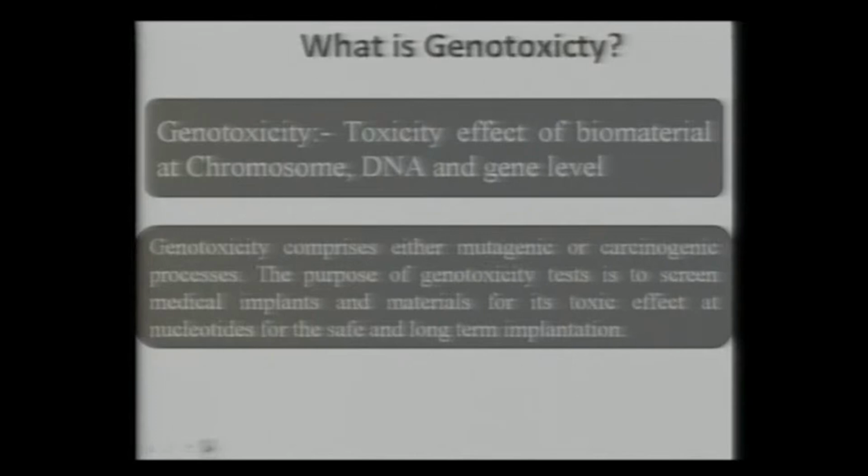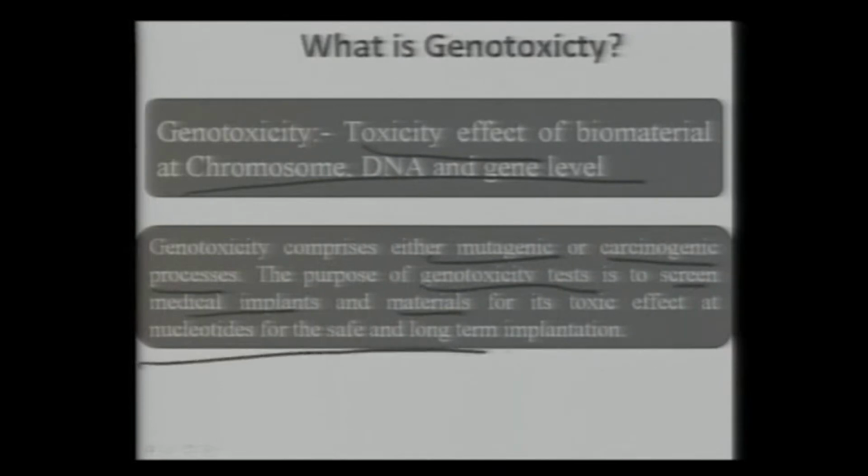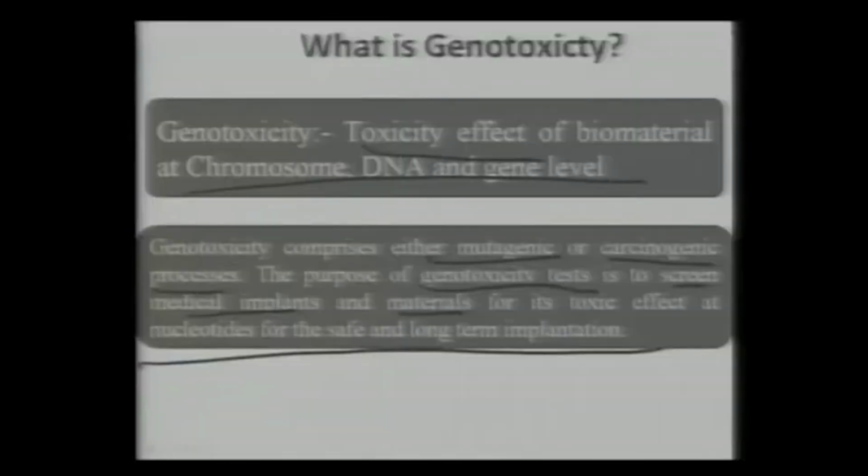This is repeated here again, that is the toxicity effect at the chromosome, DNA and gene level, and genotoxicity comprises either mutagenic or carcinogenic processes. These tests essentially screen medical implants and materials for toxic effects at the nucleotide level for safe and long term implantation. What it means is that in the long term, this material should not wear out and produce wear particles which will directly cause DNA damage. Okay, so that is what is essentially investigated here.